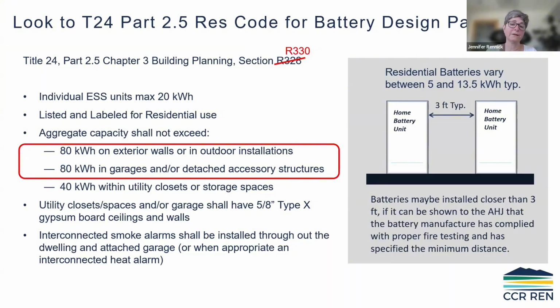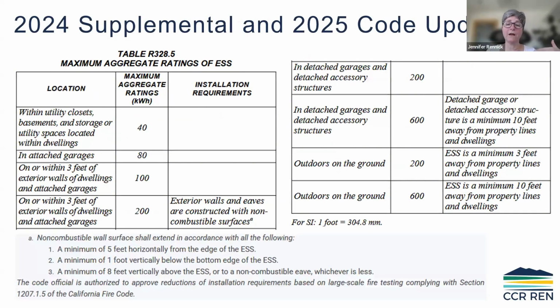And part of this is that your aggregate capacity of the battery can't exceed certain amounts of kWh, so kilowatt hour capacity. And now there's a supplemental in the 2025 code update that really spells out your maximum aggregate ratings based on a more nuanced take of where it's located. So within 3 feet of exterior wall, you can actually bump up to 100 kWh, or on exterior walls of dwellings, non-combustible surfaces, you can bump up to 200 kWh, etc.